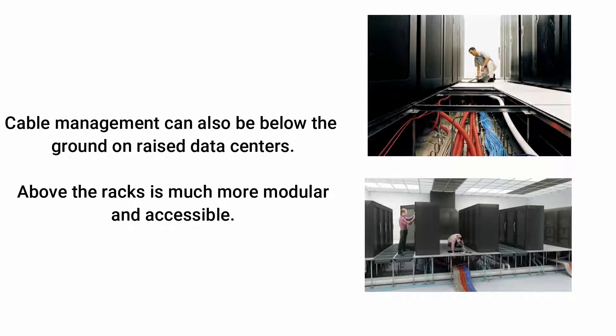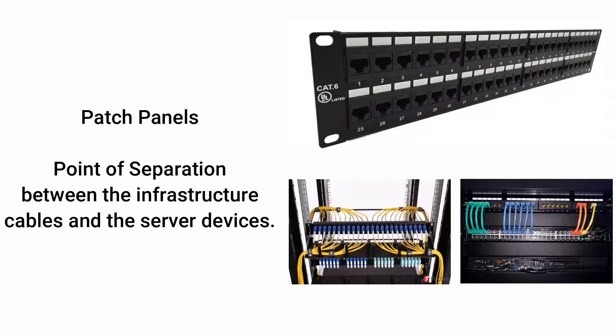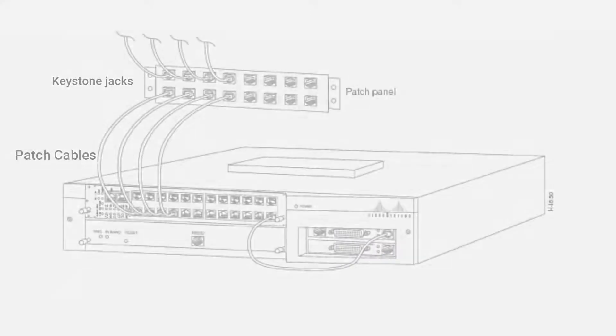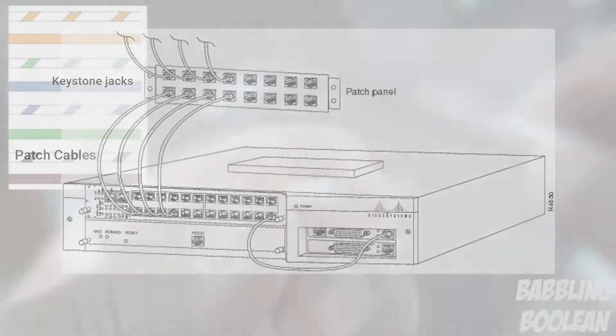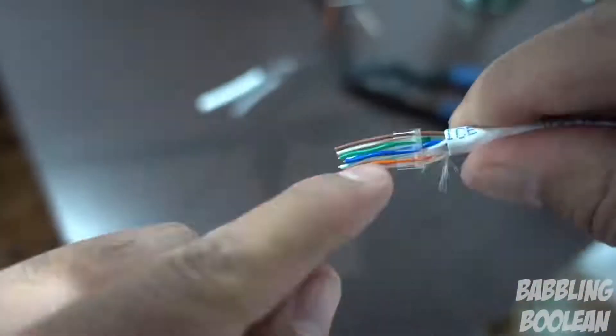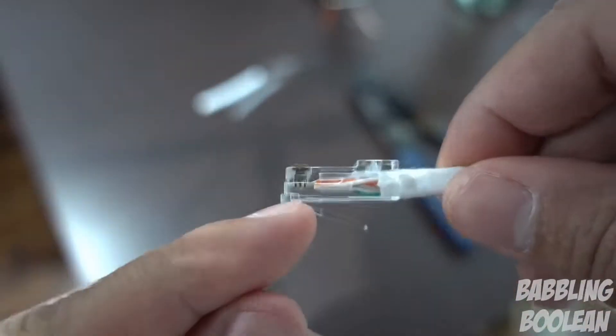Cable management can also be below the ground on raised data centers; however, above the rack, the cabling is much more modular and accessible. Patch panels are a point of separation between the infrastructure cables above or below the server racks. Patch cables connect server devices to the patch panel keystone jack, and the keystone is terminated to the infrastructure cables. Terminating a cable is the work performed to the end of a cable in order to connect it to a device.